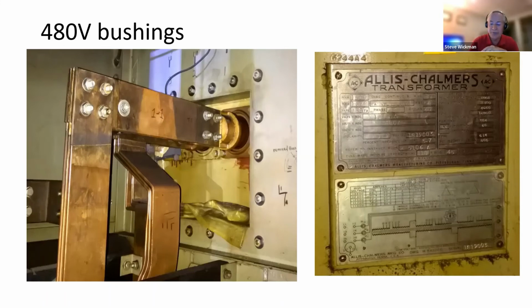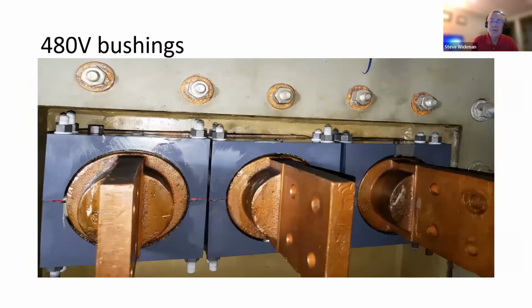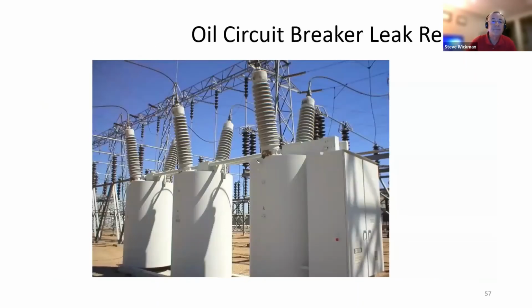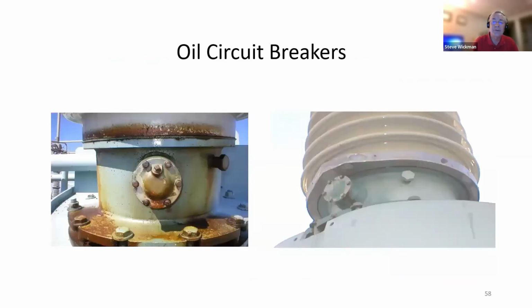480 volt bushings with gaskets that are failing. Probably original, replacement components are not to be found. And again, they didn't want to have to bring the oil down to work on these. So we fabricated PVC clamps to go around each of these 480 volt bushings to effectively contain those leaks for them. Oil circuit breakers leak just as much as transformers do, and they've got very similar components.